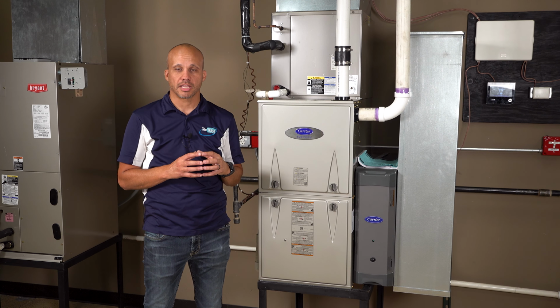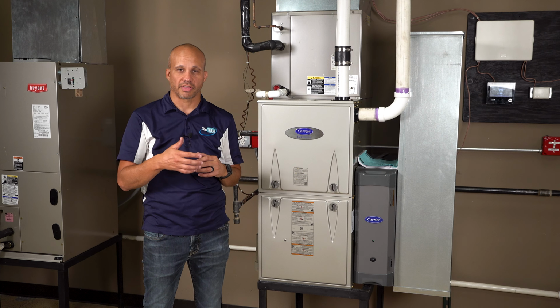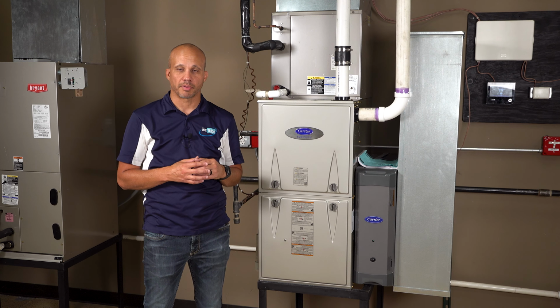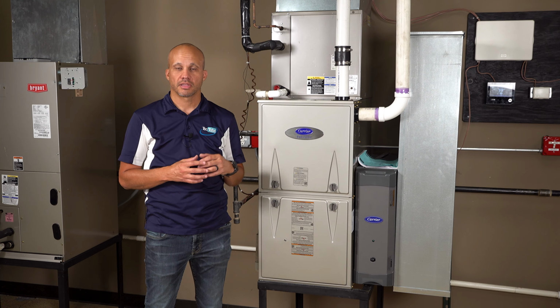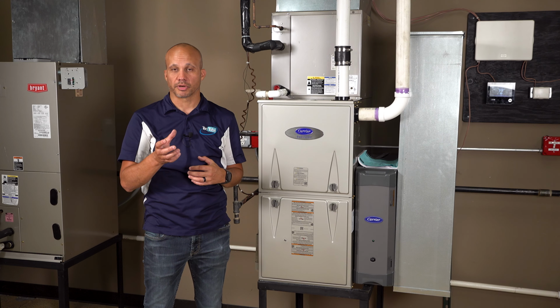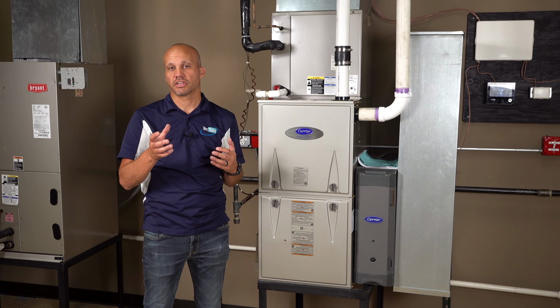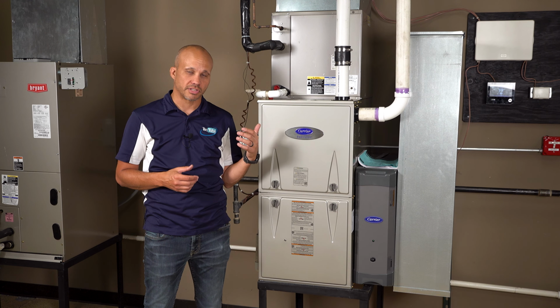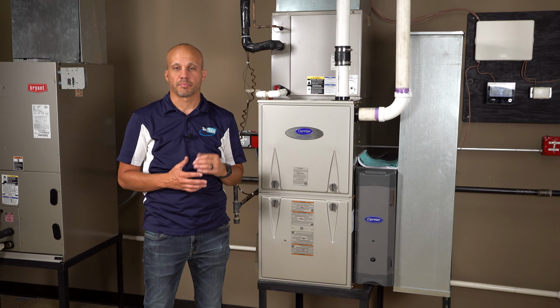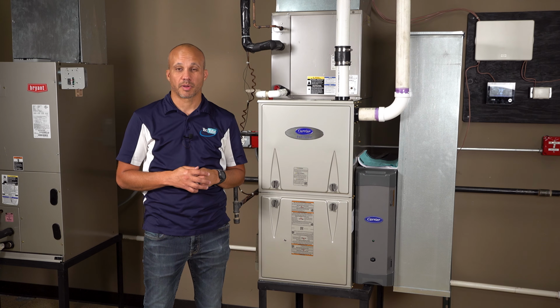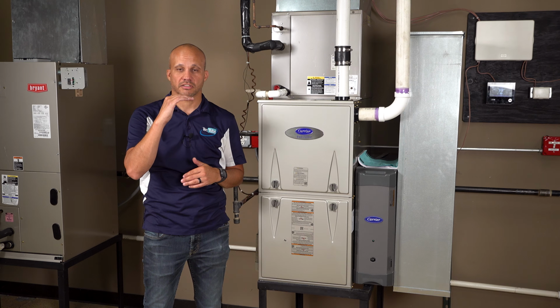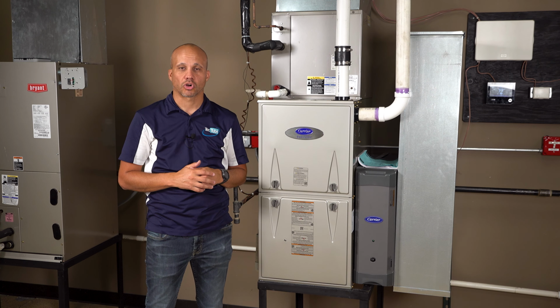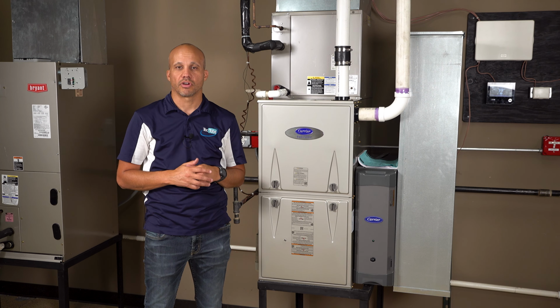So if you're doing a heat pump replacement because you want to take advantage of the low cost of running a heat pump in milder scenarios for outdoor temperature, this might be a good compromise. You run the heat pump when it's mild, 30, 40, 50 degrees outside. You run the gas-fired furnace when it's colder, negative 10, 10, 20 degrees, etc., and you get the best of both worlds. As your temperature drops outside, the heat pump becomes less efficient, whereas the furnace stays pretty much the same. So that as the heat pump gets less and less efficient, eventually becomes more costly to operate than the furnace, and then you can go ahead and run your furnace.